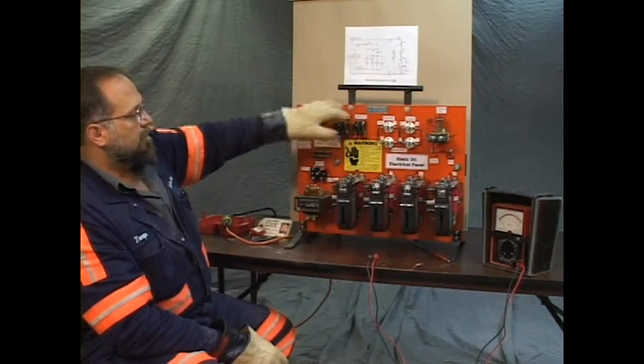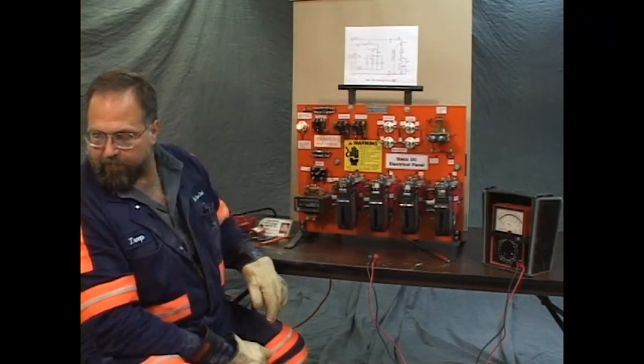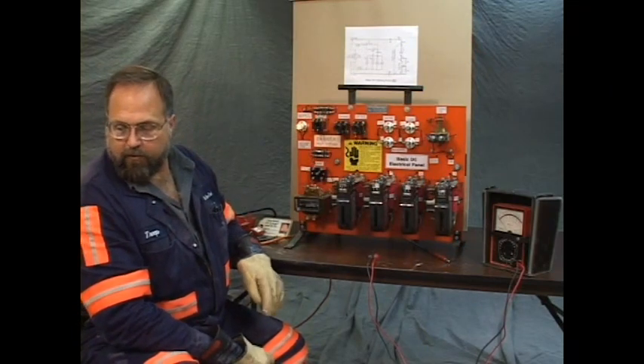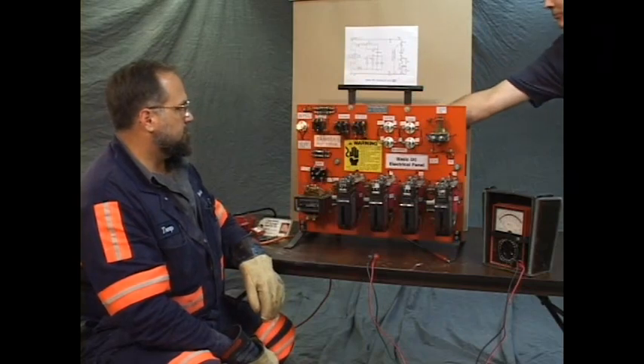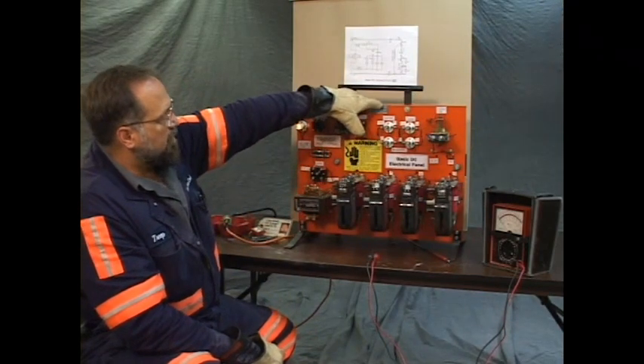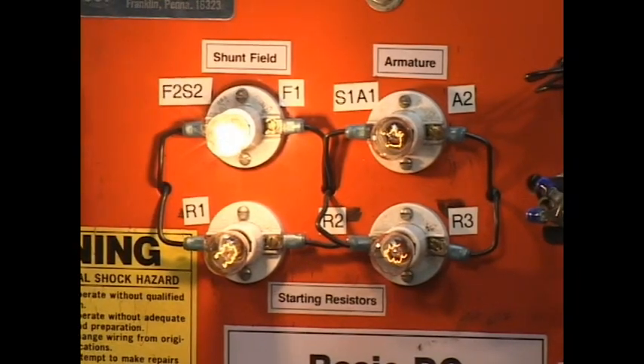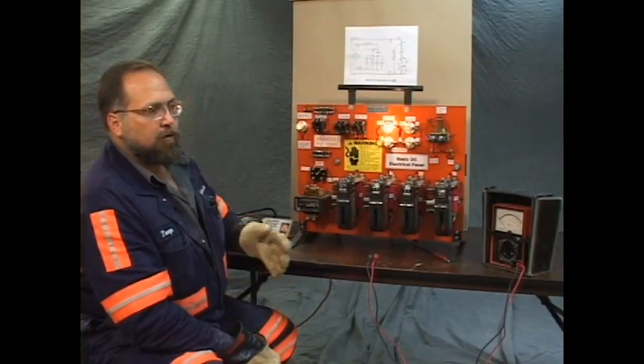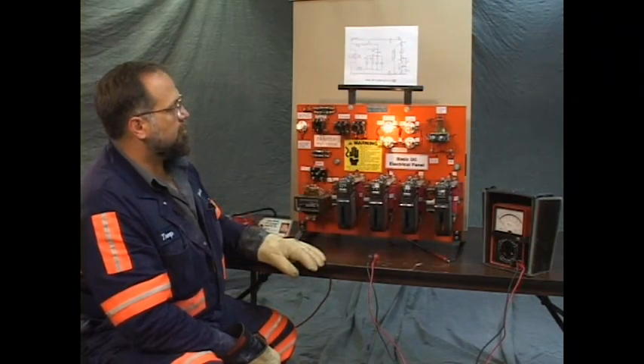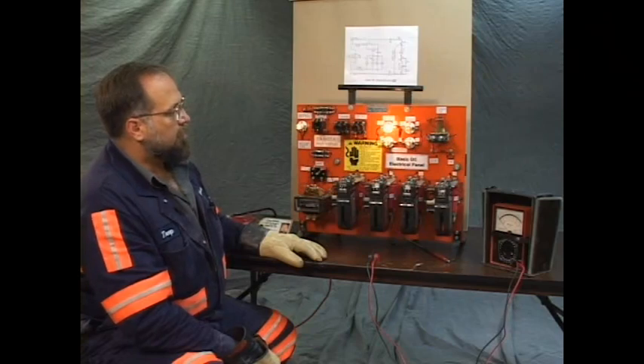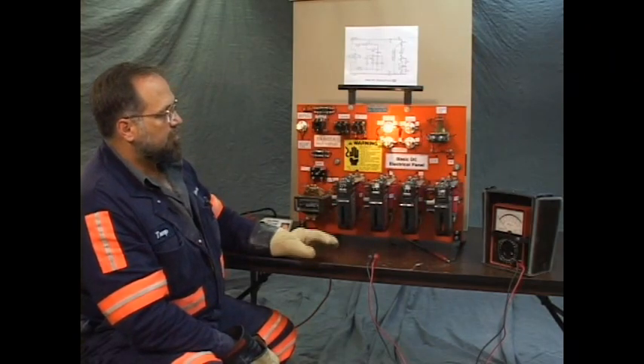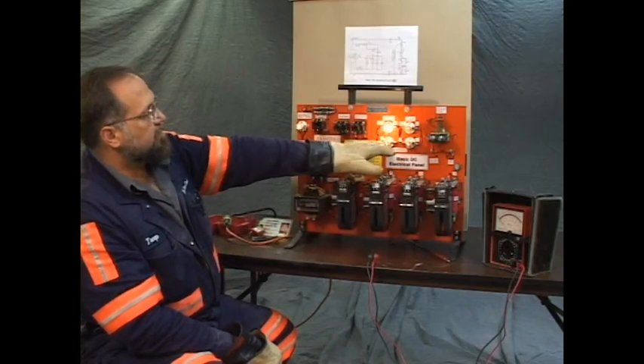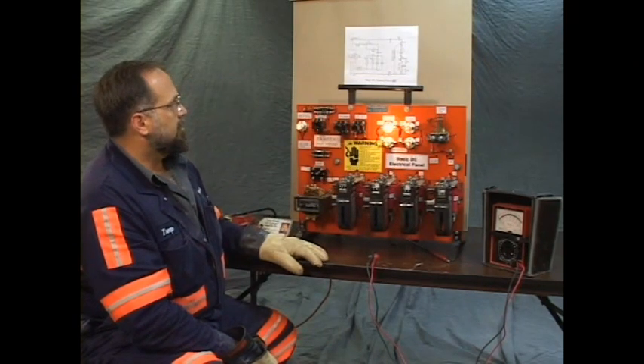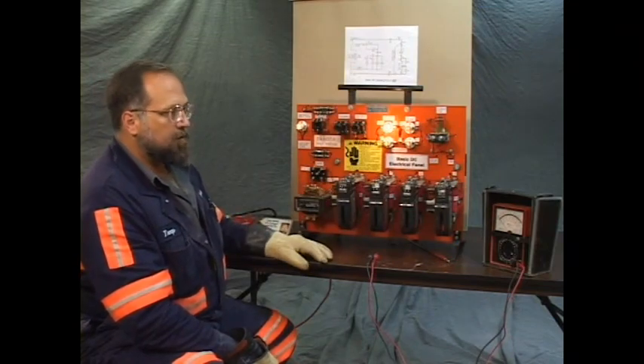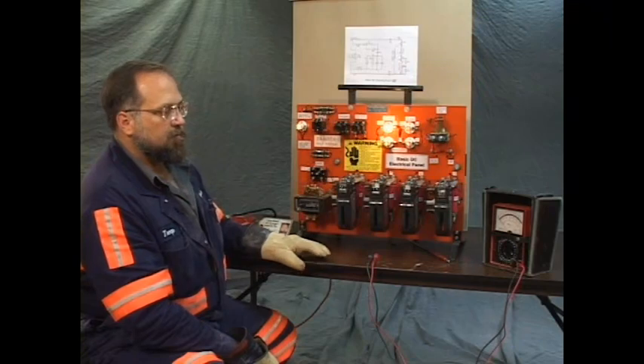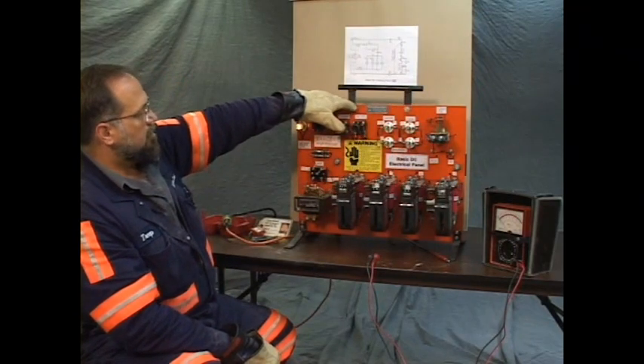And there you have it. But our problem states something somewhat different. If we'll toggle switch number 10, I'll show you the problem. You depress the start switch. And the normal progression of the panel through the cycle is interrupted. M1 and M2 close. 1A doesn't close, neither does 2A. We stay in the first step of operation. If this were on a piece of equipment, you'd only have low speed. Do it one more time.